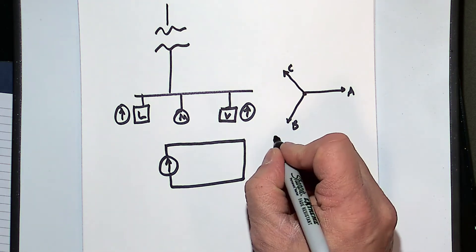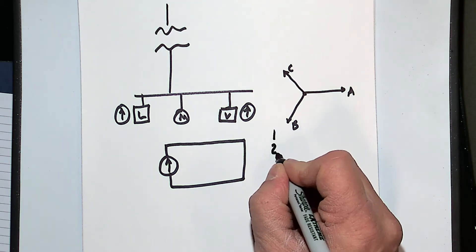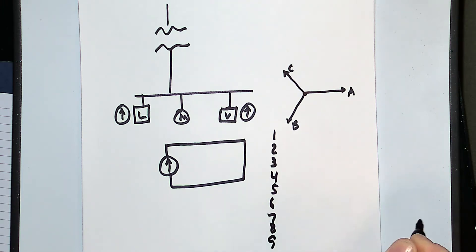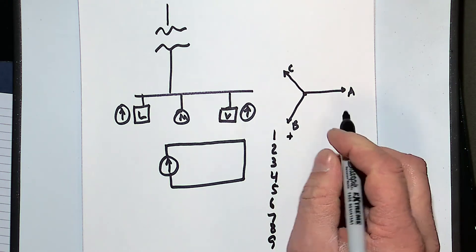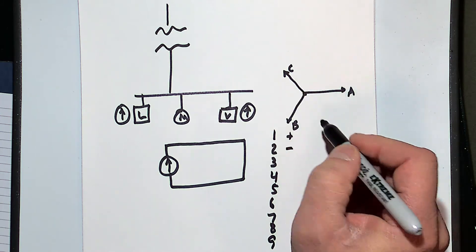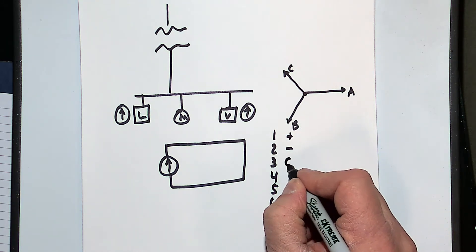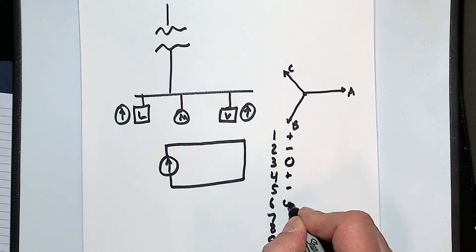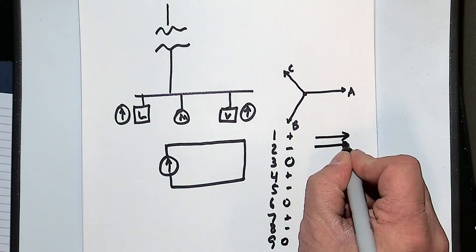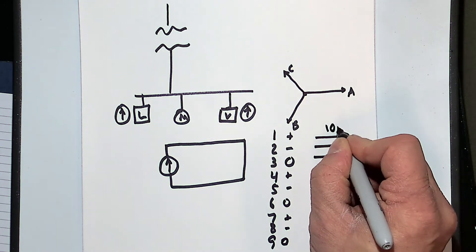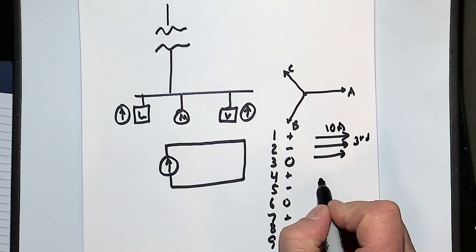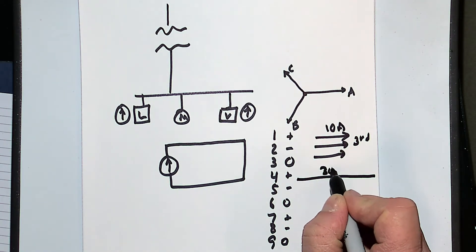If I look at the spectrum of harmonics, my fundamental is the first harmonic, then I have second, third, fourth, fifth, sixth, seventh, eighth, ninth. If we say the fundamental is a positive sequence harmonic, negative sequence flows the opposite direction. Zero sequence follows the pattern plus, minus, zero repeating. Zero sequence harmonics add up — so with A plus B plus C, if I had 10 amps of third harmonic on each phase, on my neutral I would get 30 amps.